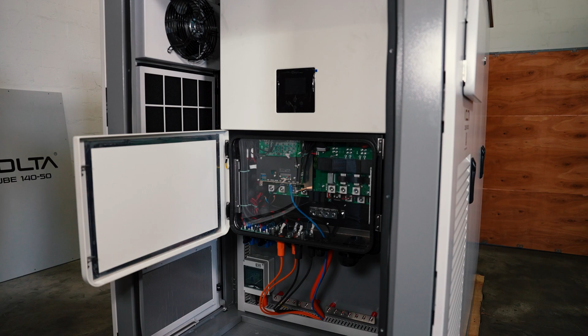Okay guys, so when you do open up your VoltaCube, you will see that your battery cabling will be done for you. Your BMS cable will be already installed. Your emergency switch will be installed and working. And then you will see your power supply to the earth leakage for your aircon. The cables will be lying inside the inverter. So when you do your AC connections, installing your output and your input, you can just wire up your AC connections for the earth leakage for the aircon on your output side. The reason for putting it on your output side is so when there's an outage, your aircon will still be working.